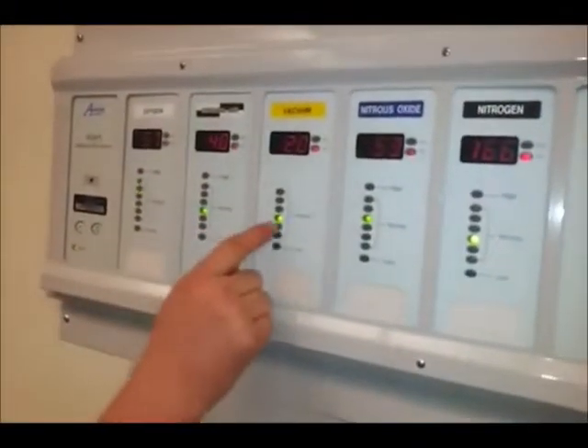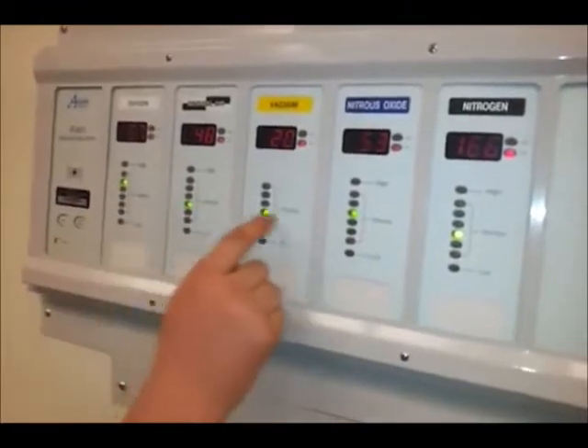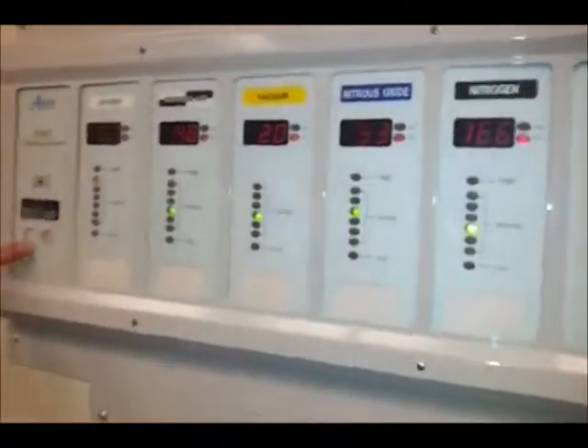The only other thing you have to check is on the wall back here, the medical gas alarms. You want all of these to be within the normal range. So basically you want them green. To test it, there's a little test button on the side. You hit that, and yeah, they're all green. So we're good to go.